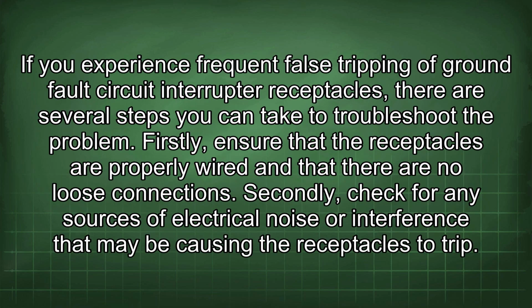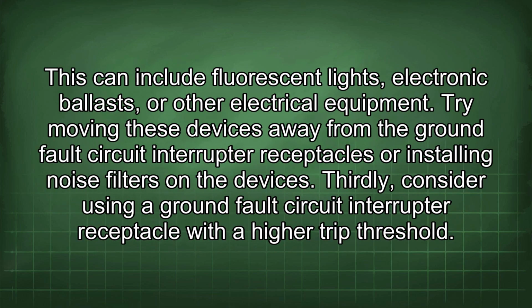If you experience frequent false tripping of ground fault circuit interrupter receptacles, there are several steps you can take to troubleshoot the problem. Firstly, ensure that the receptacles are properly wired and that there are no loose connections. Secondly, check for any sources of electrical noise or interference that may be causing the receptacles to trip. This can include fluorescent lights, electronic ballasts, or other electrical equipment. Try moving these devices away from the ground fault circuit interrupter receptacles or installing noise filters on the devices.